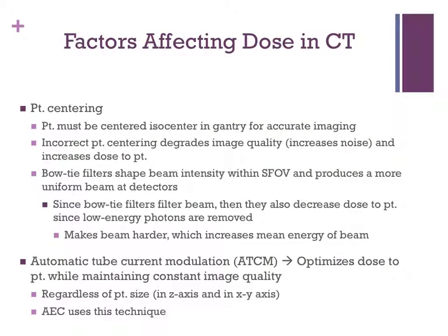With patient centering, the patient must be centered at isocenter in the gantry for accurate imaging. Incorrect patient centering degrades the image quality and also increases noise, and this increases dose to the patient as well.